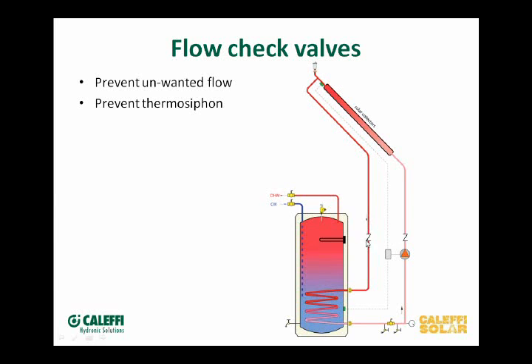Flow check valves: when you have your collector above the tank and you've got a hot tank and a cold collector at night, you're going to thermally siphon heat away. It's important to have check valves on both sides — supply and return. Some guys say their pump has a built-in check valve, but that only takes care of one side. You can get flow going both ways through a single pipe, where cooler water drops down the center and hotter water goes around the outside. I highly recommend a spring check rather than a gravity gate type, since I've seen those seep through if the water is hot enough.